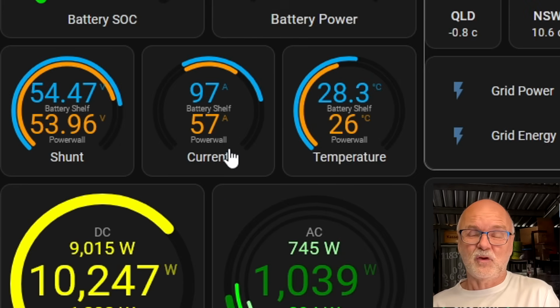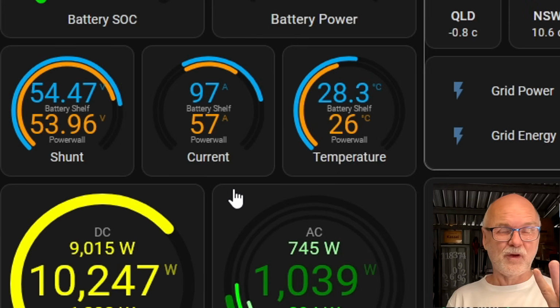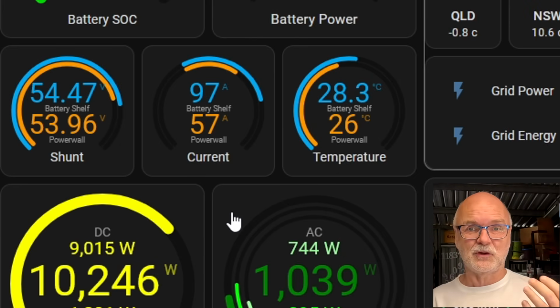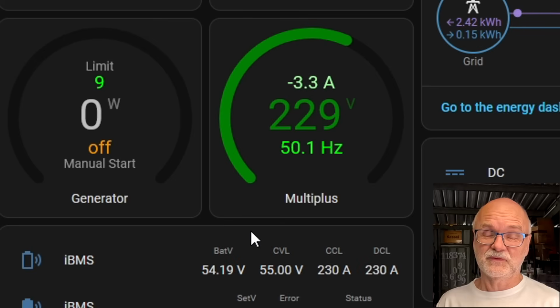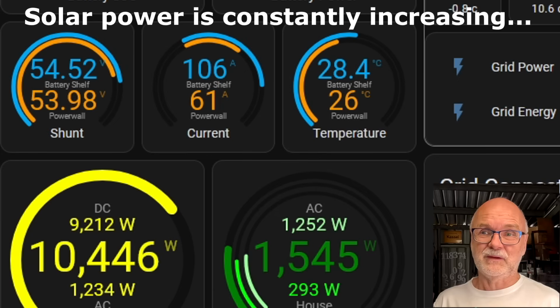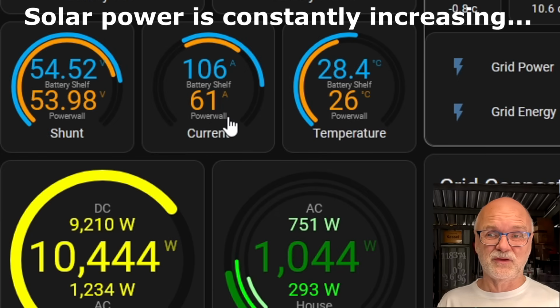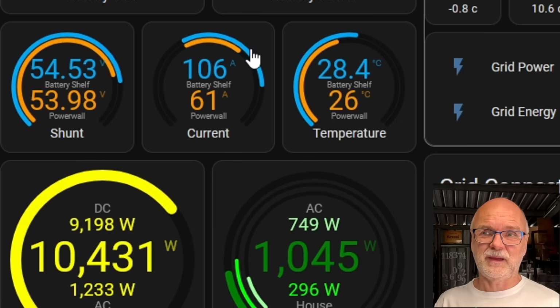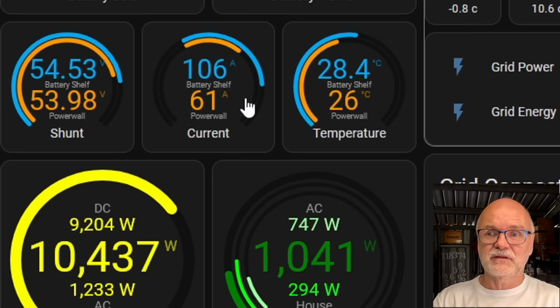We have already limited the current by 4 amps, and we are under 60 amps now, so the automation is pausing. It has reduced the charge voltage limit down to 55, and we're still over 61 amps, so I think we'll go down a bit further. 106 amps into the battery shelf, 61 into all the other batteries, so we should see 54.9 at any moment.